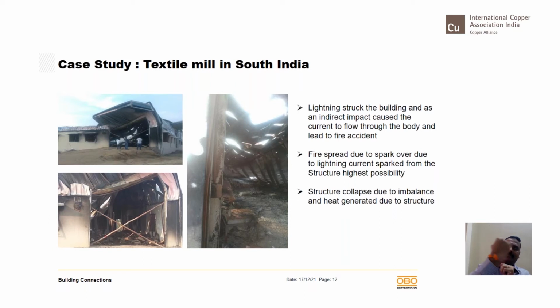This particular industry was making pillow materials, like the rayon material inside the pillow. The materials were stacked vertically, not horizontally, till the top. So the fire easily penetrated through all the material kept here. And remember, when I went to the site to investigate and take photographs, we checked with the firemen there. They gave the information that the temperature inside the building when they arrived was about 1700 degrees. So they could not enter the premises for at least 2.5 hours, till the fire was put out from outside. So a small lightning strike created such big havoc and such complete collateral damage to the structure. This is possible if the system is not equipotentially bonded.